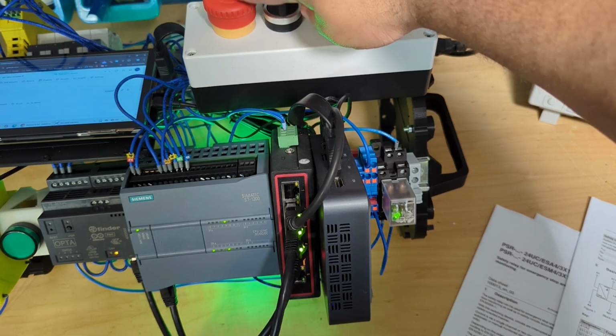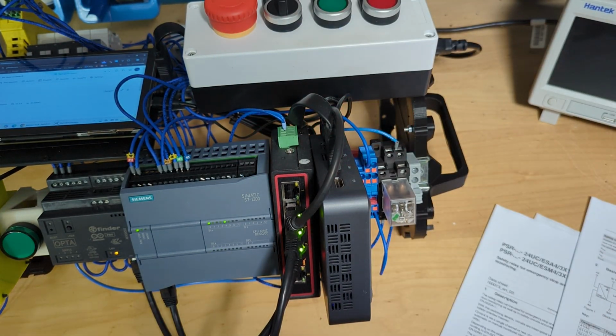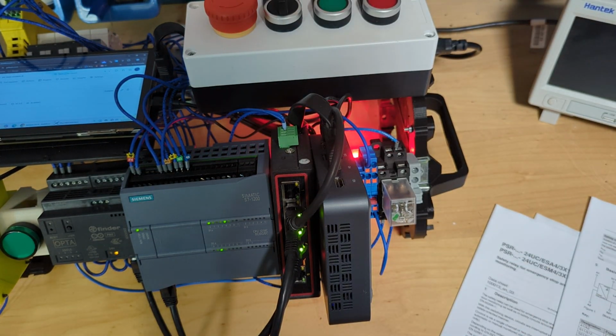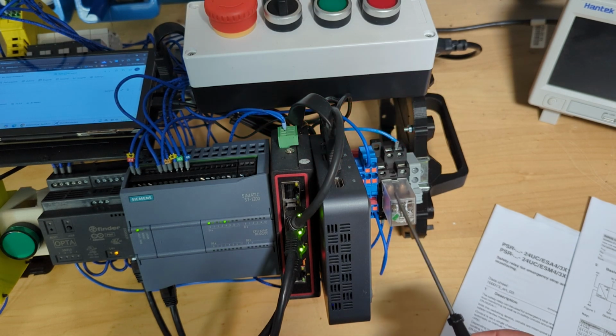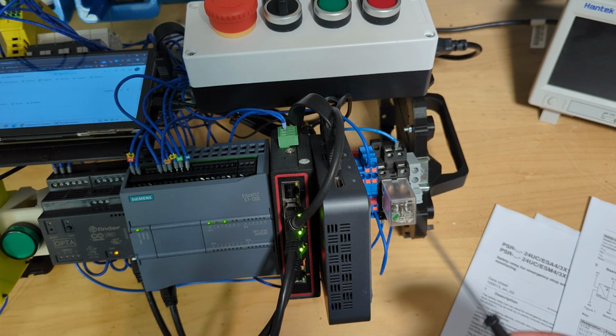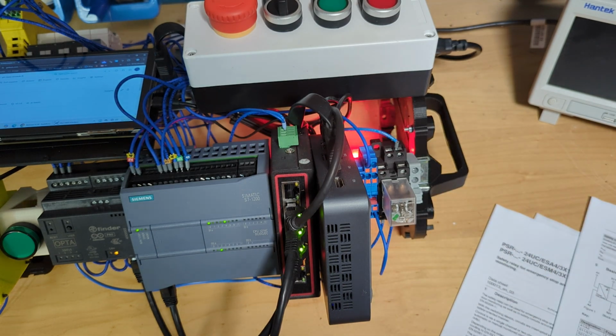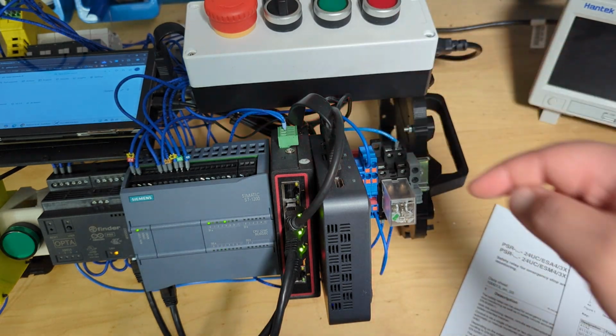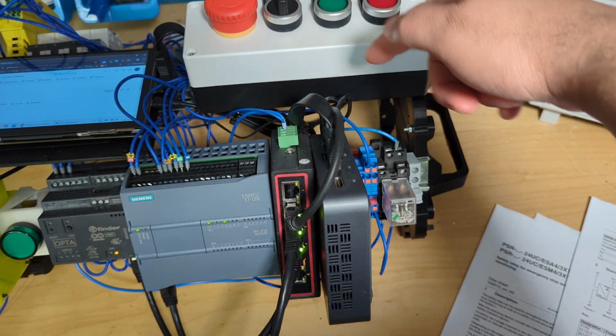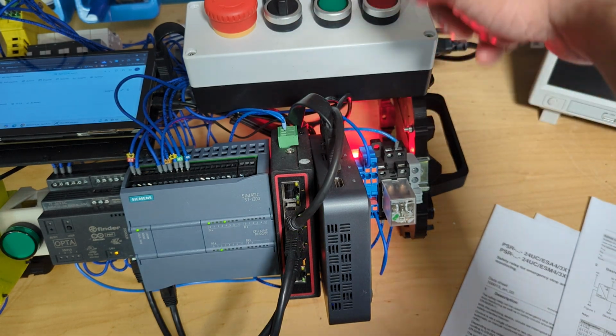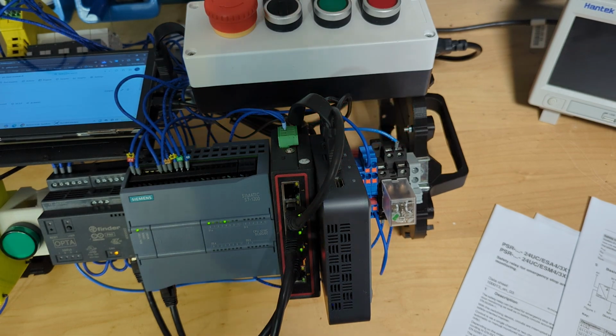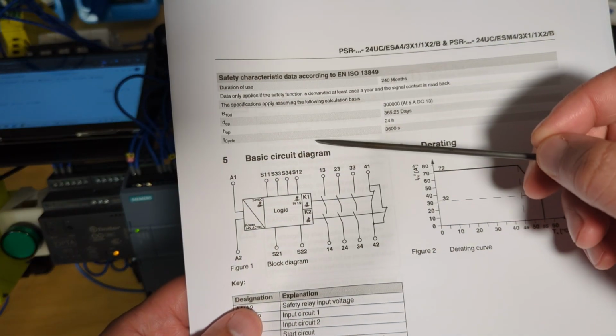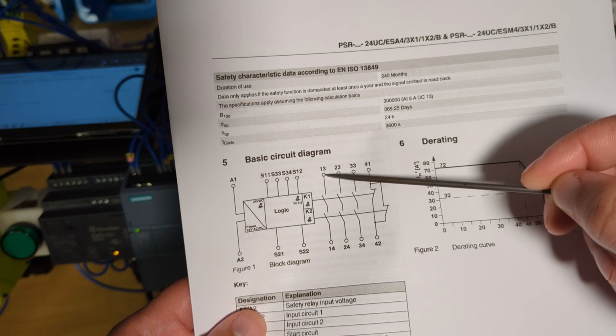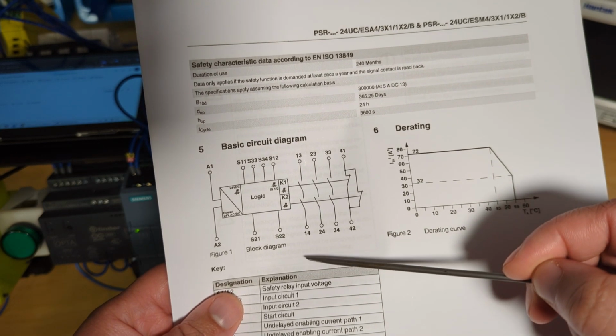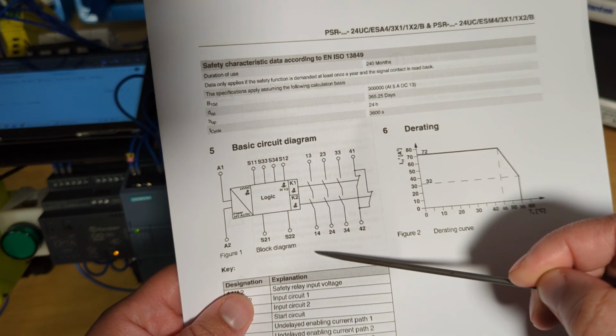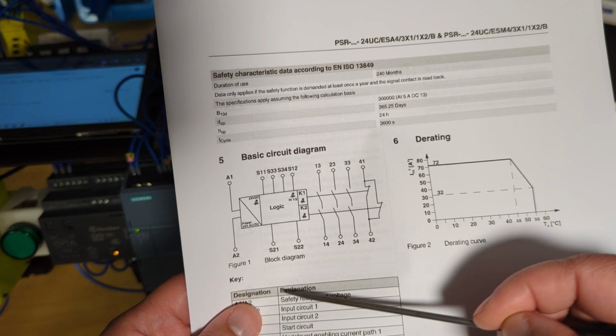If I hit the e-stop now, this turns off that normal relay. So this is just a standard 24-volt coil relay, and I would use it to drive, for example, a motor. I've got my 24 volts coming from my 24-volt power distribution on the other end, going into my safety relay. So it goes 24 volts into 13, and then out from 14 is where I connect, for example, a motor or a valve, and the other end I ground, put to 0 volts.